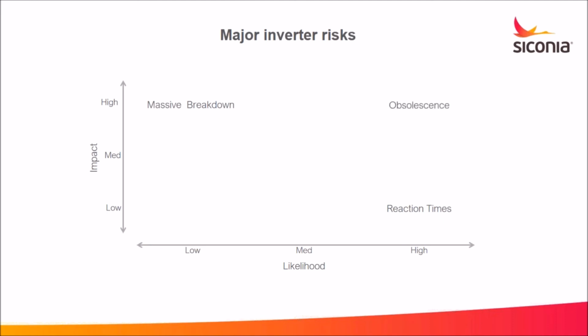The third and most important risk for the inverters is the obsolescence. This is the inability of the manufacturer to repair the inverter after a failure and keep it performing as day one of operations. These problems are caused mainly by the lack of components and spare parts inventory. Some years after an inverter model has been discontinued, the manufacturer could struggle to get the same or compatible components from suppliers. A component redesign most of the times is not performed because the manufacturer is focusing R&D teams on new technologies instead of old products.